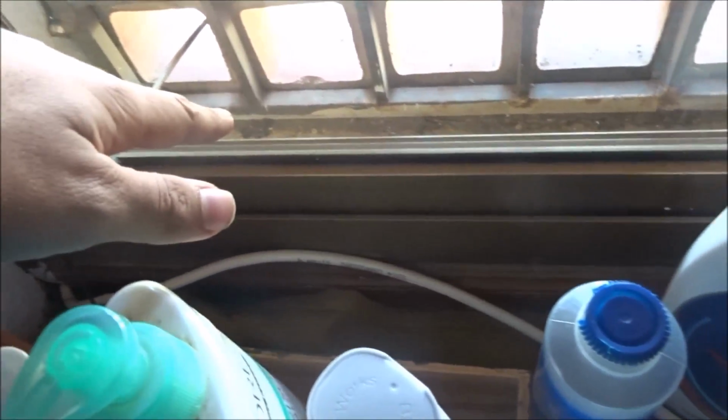So now we're going to test the direct intake temperature coming into the unit from the outside into the condenser coil. So we're going to check that. I expect it to be 85 degrees, 84 outside right now. So let's check that out. Okay, got the sensor right in the intake. See it right here real quick. That's where the AC unit actually sucks air.